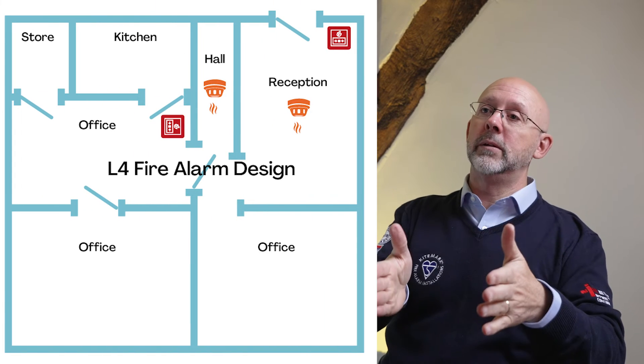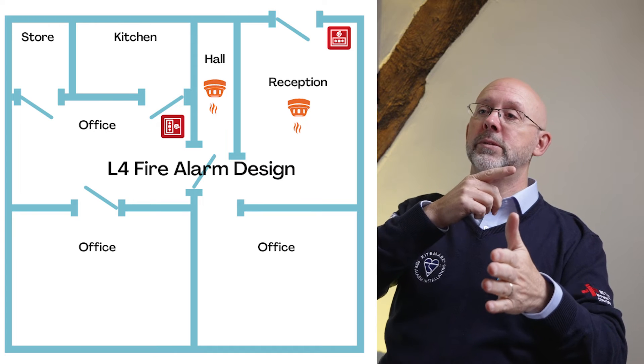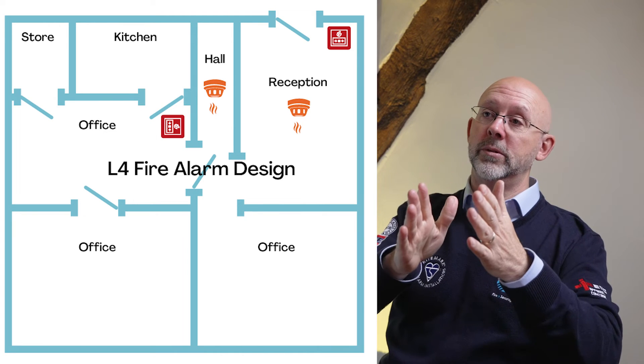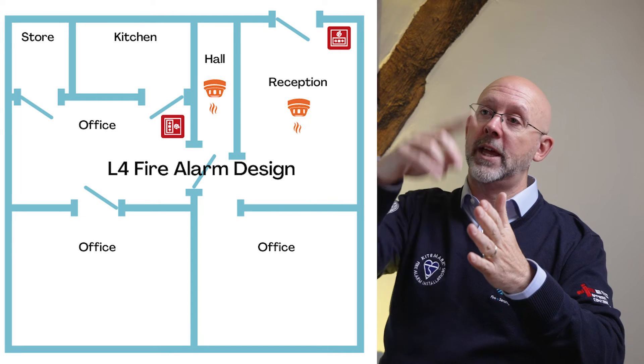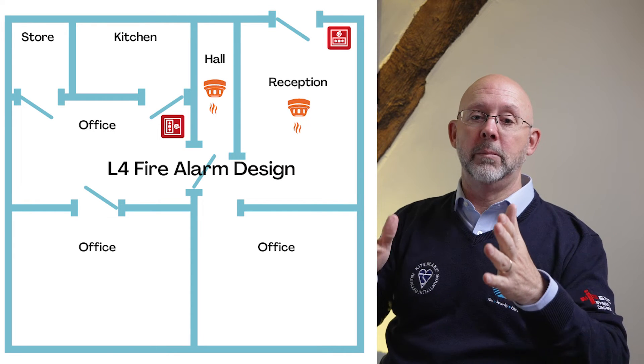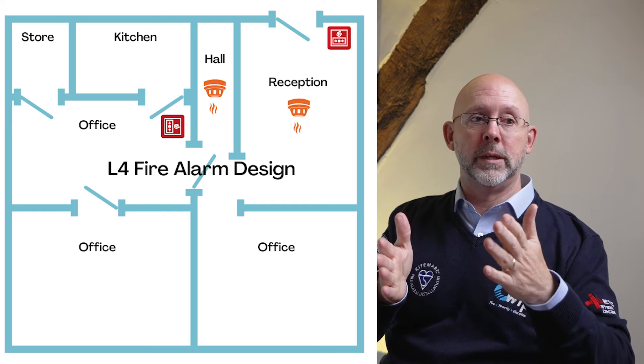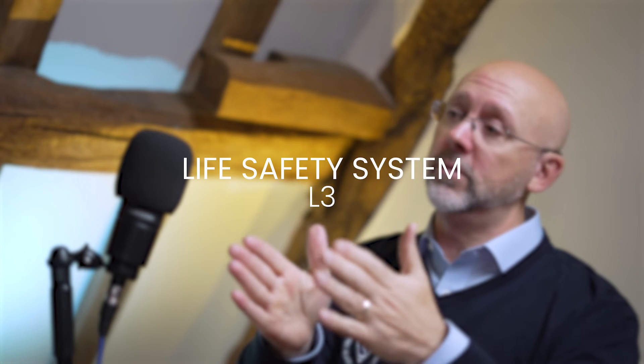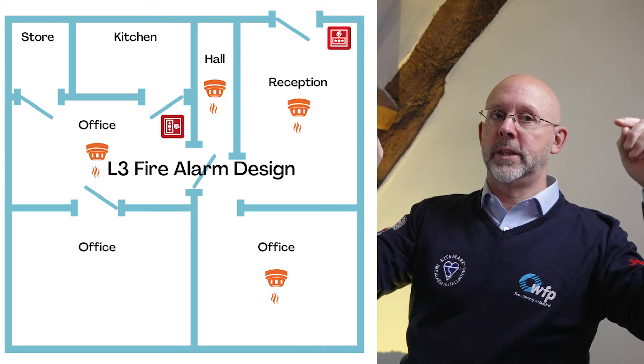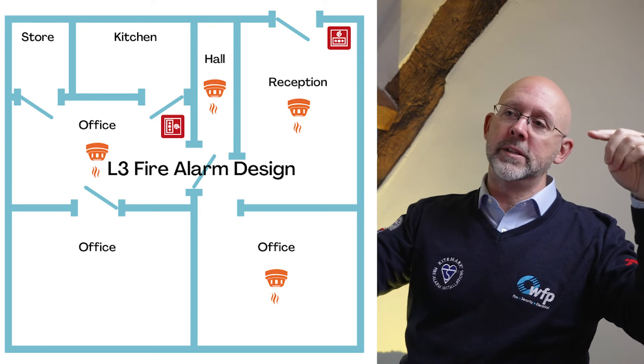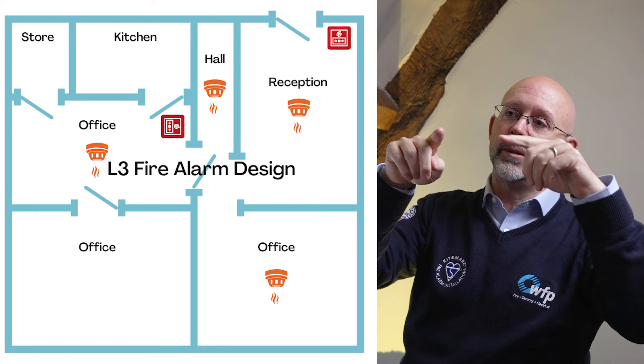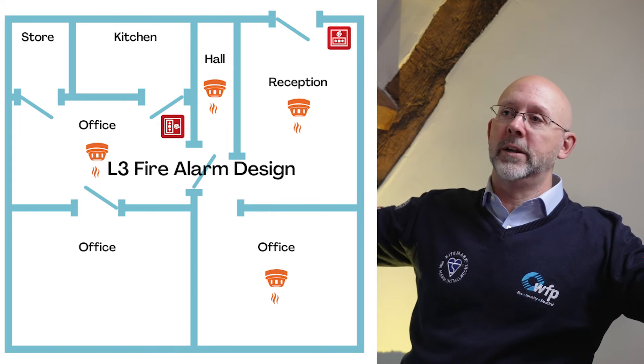L4 is like an office building or a school where you put smoke detectors along the corridors only — none in the rooms, just in the corridors and on the stairs covering the escape route to the door. L4 didn't exist until about five or six years ago. L3 is the same as L4 plus detectors in the rooms that open onto those escape routes. Smoke detectors cover a seven-and-a-half metre radius, but with L3 you're only concerned about smoke leaking out of a room into the escape route.